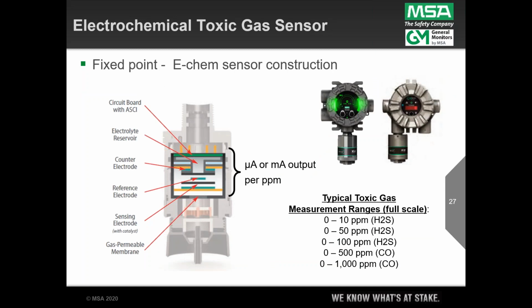Well, think of it as a micro fuel cell. And what do you mean, like a battery? And the answer is yes. The construction is shown there on the left. You've got a cavity, and in the cavity is electrolyte, and also in that cavity are electrodes, right? We have a sensing electrode and a reference electrode, but instead of being a sealed battery, this electrochemical sensor has a permeable membrane on the face of it. And what does that permeable membrane do? It allows vapors to permeate through the membrane and into the cavity. And what happens in the cavity when the specific gas or the analyte to be measured permeates through there? It creates a microcurrent flow between the electrodes.